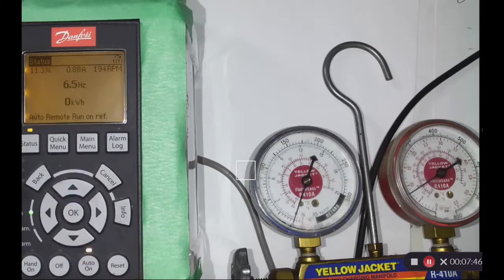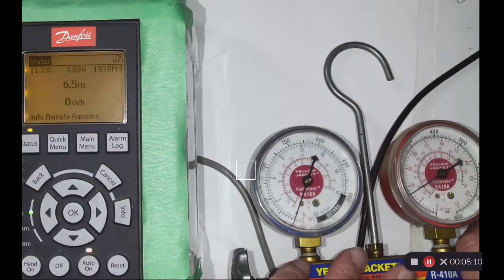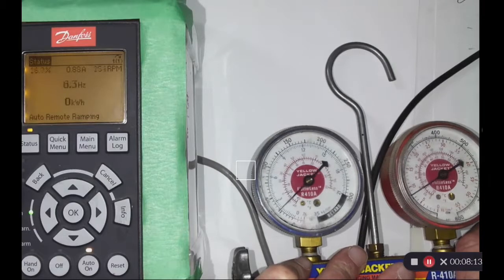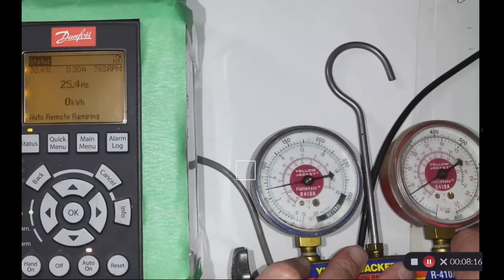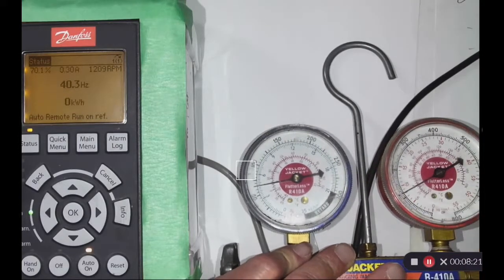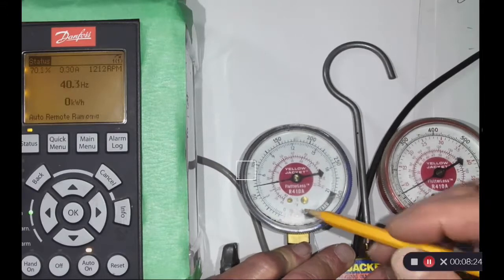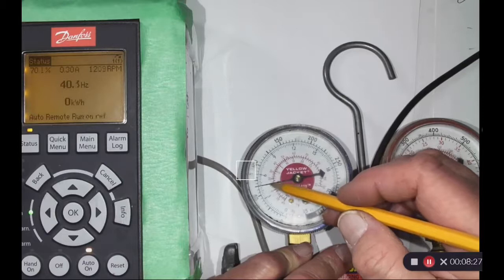And it's turning because the minimum output of the transducer is 4 milliamps. So it's turning at 11.4%. That's where it's at, because 0 to 20 is essentially what it's looking at. So what we're going to do then is give it a little bit of gas pressure over to the low side, and so my low side pressure is around, I'll call it somewhere around 70 pounds, 60 pounds.